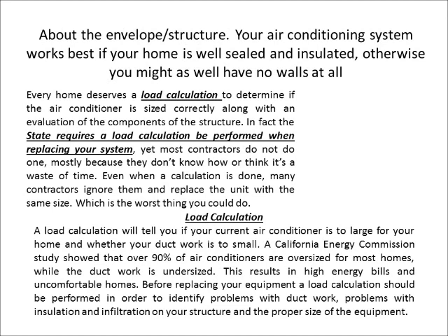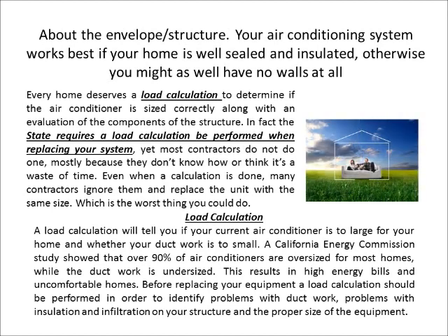Your air conditioner system works best if your home is well sealed and insulated — otherwise, you might as well have no walls at all. To determine what you need, we do what we call a load calculation. Every home deserves one. It determines the correct size of the air conditioning along with other components so we can tell what needs to be done. The state of California requires a load calculation to be performed when replacing your system, yet most contractors do not do one — mostly because they don't know how or think it's a waste of time. And even when it is done, many contractors ignore it and replace the unit with the same size, which is the worst thing you could do.